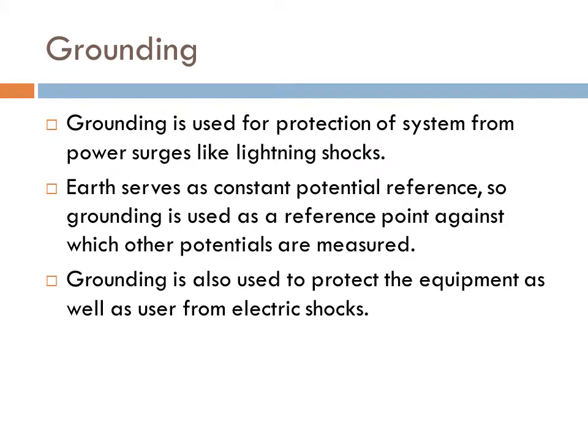Grounding is the main part in a protection system. Grounding is used usually for protection of system from power surges like lightning shocks. Earth serves as a constant potential reference. So grounding is used as a reference point against which other potentials are measured. Grounding is also used to protect the equipment as well as user from electric shocks.